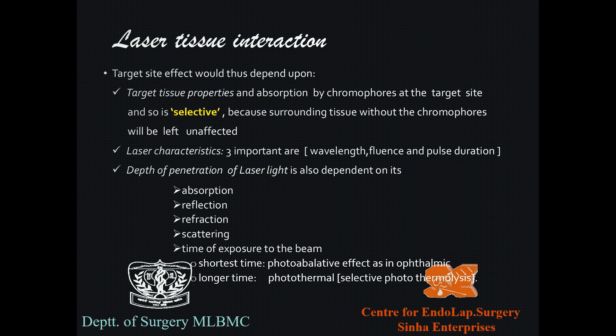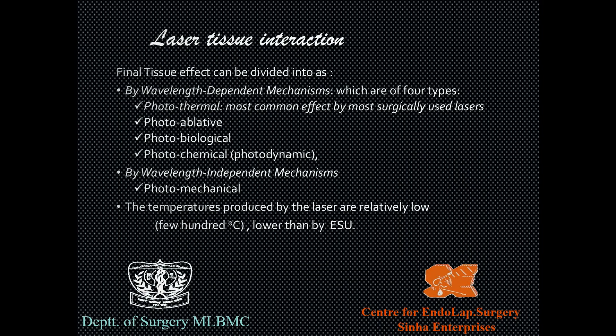Laser-tissue interaction can be divided into wavelength-dependent mechanisms and wavelength-independent mechanisms. Wavelength-dependent types include: (1) photothermal — tissue heated after laser application, the most common effect by surgically used lasers; (2) photoablative — tissue removed without heating; (3) photobiological effect; and (4) photochemical or photodynamic effect. The wavelength-independent type is the photomechanical effect. Maximum temperature achieved with laser is around 200°C, lower than electrosurgery's 300–400°C.